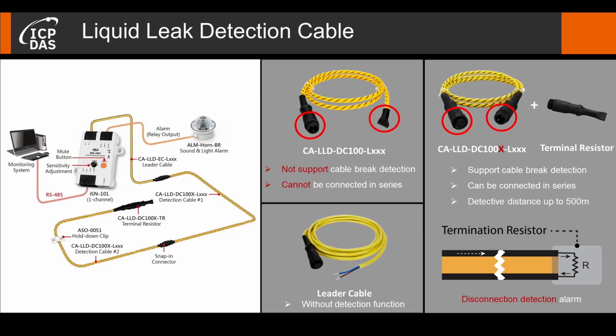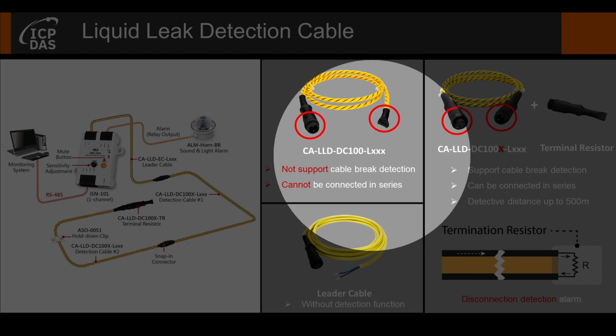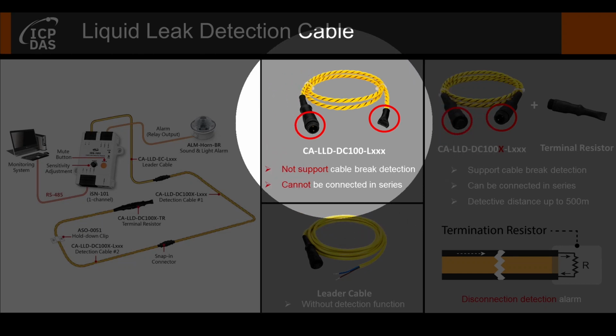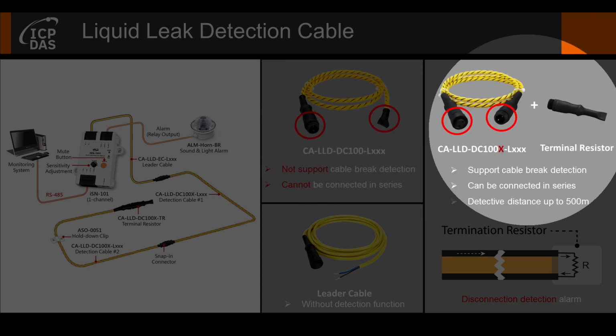ICP DAS provides two different liquid leakage detection sensing cables. Both of the two sensing cables can be used to detect the liquid leakage. However, the cable on the left side doesn't provide the cable break detection function and cannot be connected in series. By contrast, the cable on the right side can be connected in series. In addition, with terminal resistor, it can be used to detect cable break.